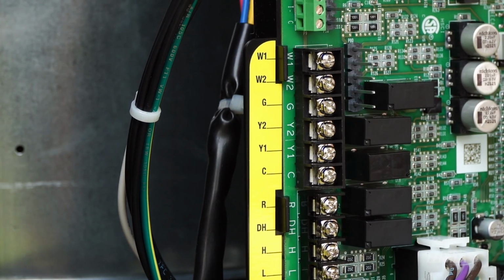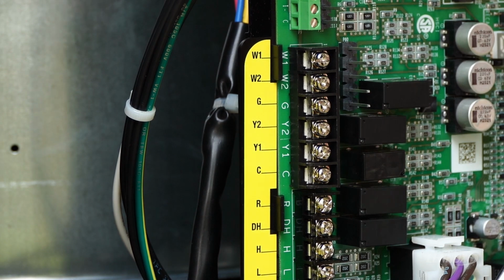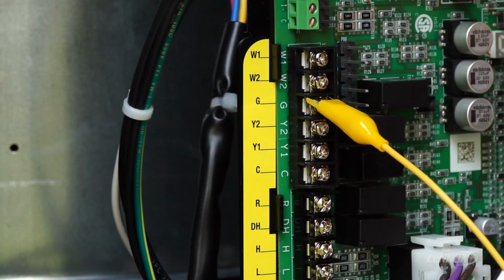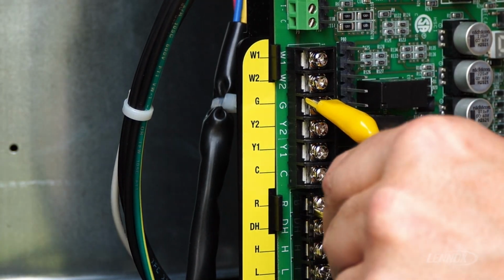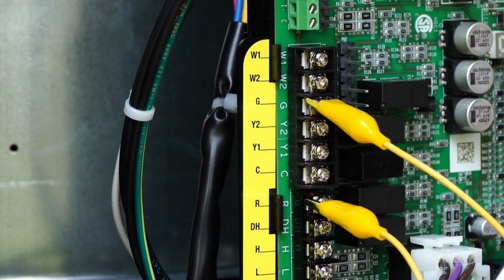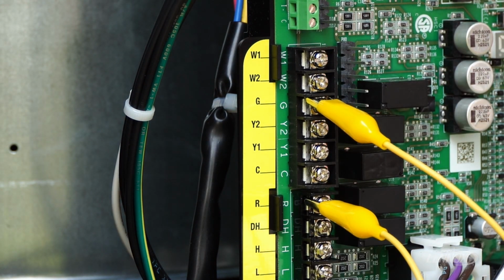For a best practice, let's see if the blower motor will start. First, we put our jumper on G, then the other end of the jumper on R, just to see if we can get the blower motor to start before we put all the wiring back together. And here we go, blower motor's on and running.